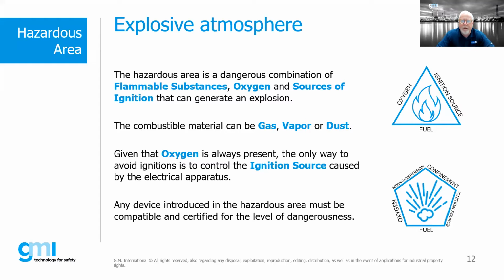So it's not just electrical arcing and sparking devices in industry that we need to be concerned with. The important thing is that when we think of the various protection concepts, we really have to focus our attention on the ignition source, because we're assuming our EX equipment is going into an environment where oxygen is present. If we removed oxygen completely, it would be a very difficult place to work. So we focus attention on the ignition source, or on reducing the amount of gas, vapor, or dust present in the environment.